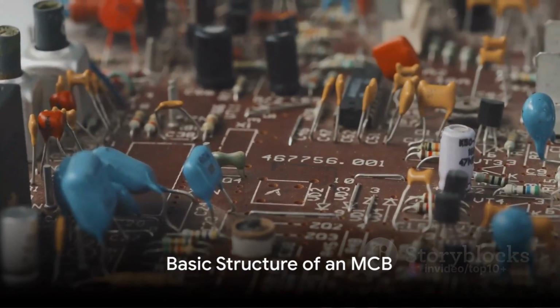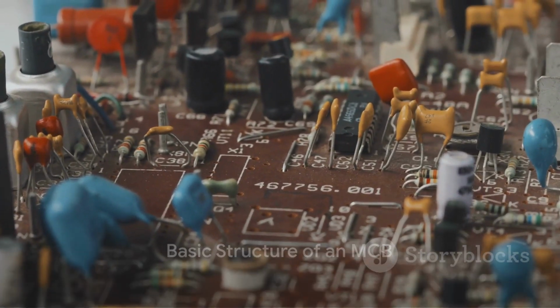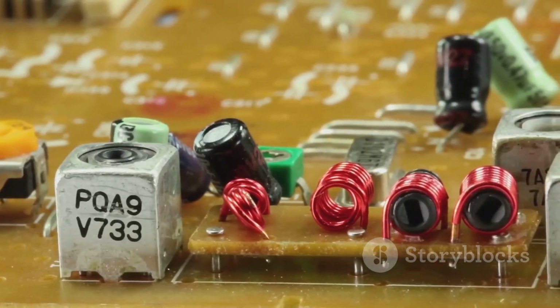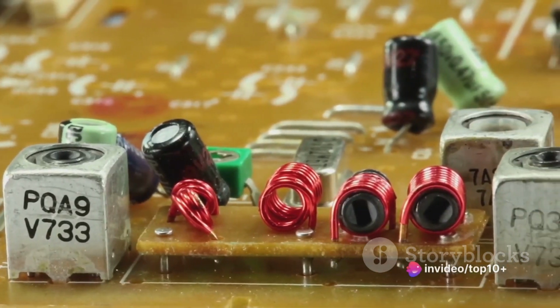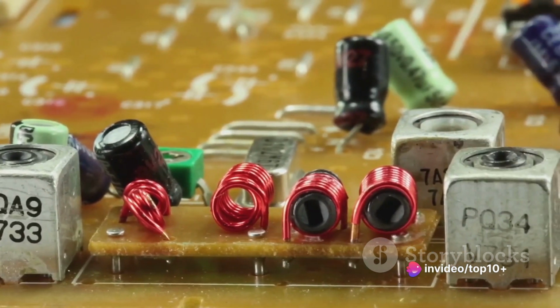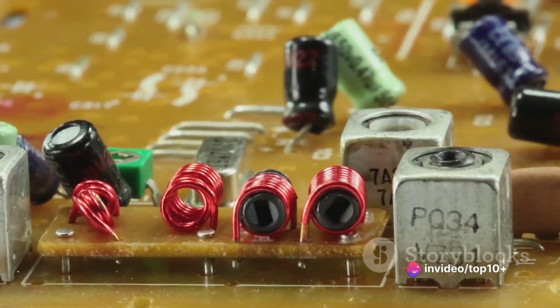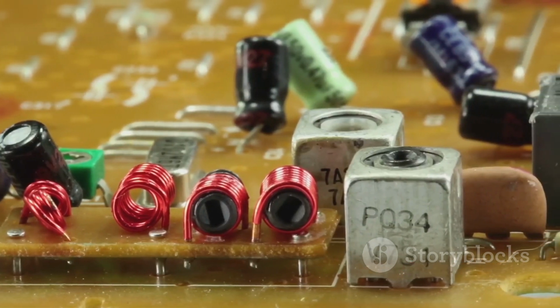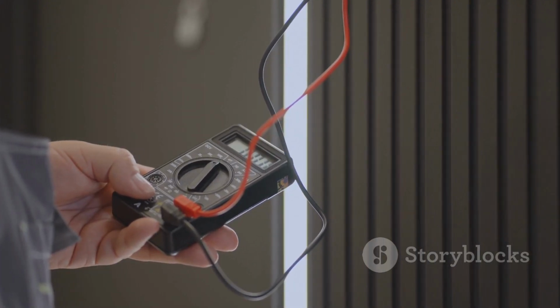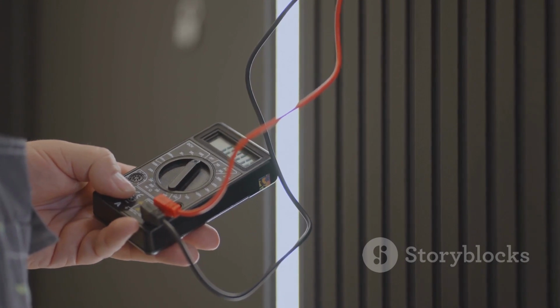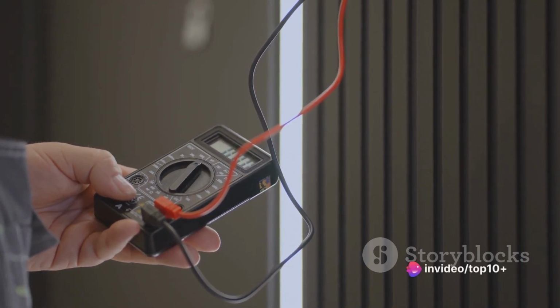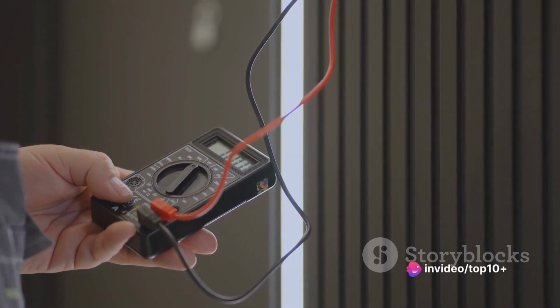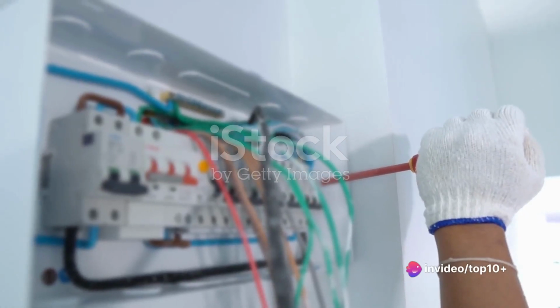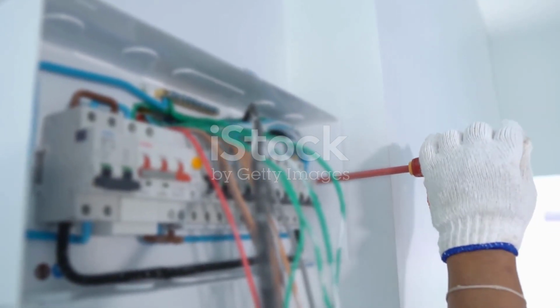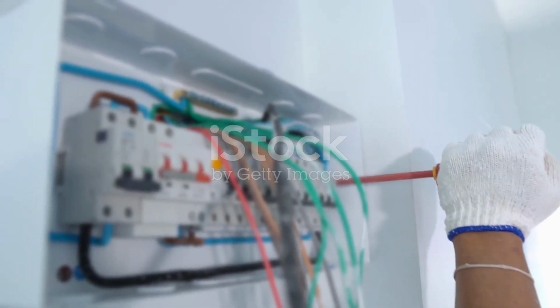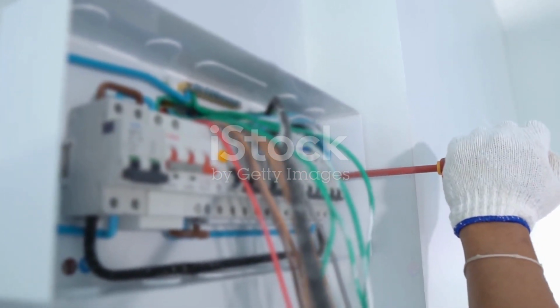To understand how an MCB works, we need to first familiarize ourselves with its structure. The miniature circuit breaker, or MCB, is a cleverly designed device made up of three core components: the trip unit, the operating mechanism, and the arc extinguisher. Let's start with the trip unit. This is the brains of the operation. It's the part of the MCB that monitors the flow of current through the circuit. When everything is running smoothly, the trip unit remains inactive. But when it detects an overload or short circuit, it springs into action, triggering the operating mechanism.